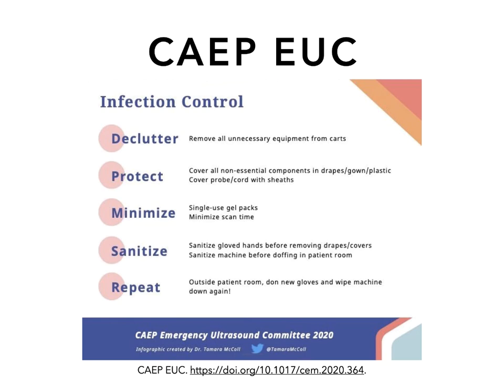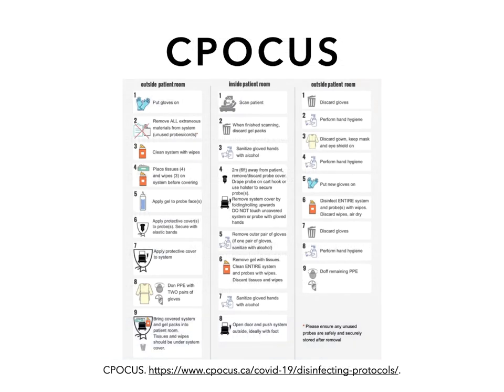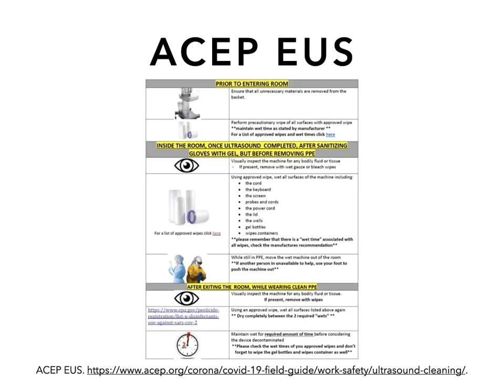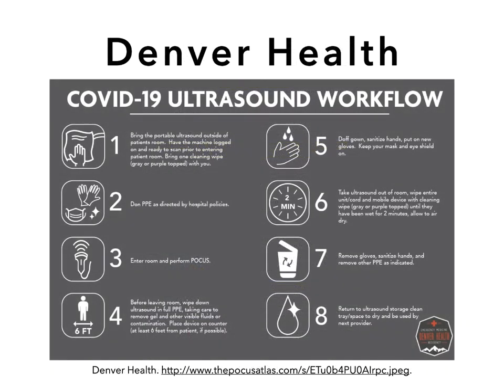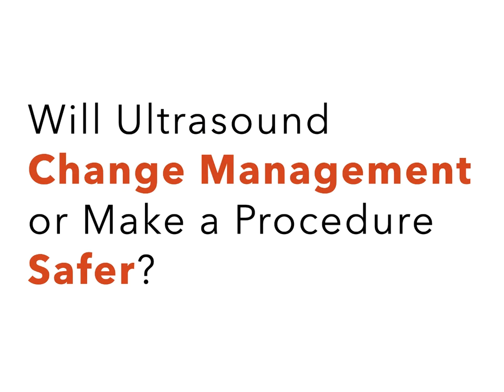Ensure that your department has a standardized infection control workflow so that everyone is following the same protocol. The Canadian Association of Emergency Physicians Emergency Ultrasound Committee has published an infection control protocol freely available online. The Canadian Point of Care Ultrasound Society has protocols for both cart-based units and handhelds. The American College of Emergency Physicians Emergency Ultrasound Section has created a one-page protocol. The Emergency Ultrasound Team at Denver Health Medical Center has created a great infographic. The machine should be cleaned both in the patient room immediately after use and outside the room after removing PPE. Before you take the machine into the room, ask yourself: do I have a clinical question that ultrasound can answer? If no, don't scan the patient — this is not the time to be doing practice scans or scanning just for fun.